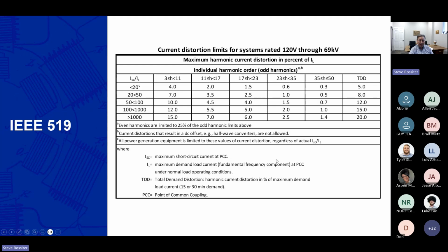The standard now is somewhere around 20%, where if you're a manufacturer, Sylvania or Philips or whoever, one of the specification points is that we're going to be below 20%. And that's pretty common for them. It's easy in a little fluorescent driver to have some active harmonic cancellation to get that down, so it doesn't cost them a whole bunch of money. But when you get into a 1,000 horsepower variable frequency drive, dealing with thousands of amps, that's a much more difficult issue. So if there are any questions about IEEE 519, I don't want to spend too much time on that, but that is an important thing. That is the recommended practice that tells us what we're trying to do.